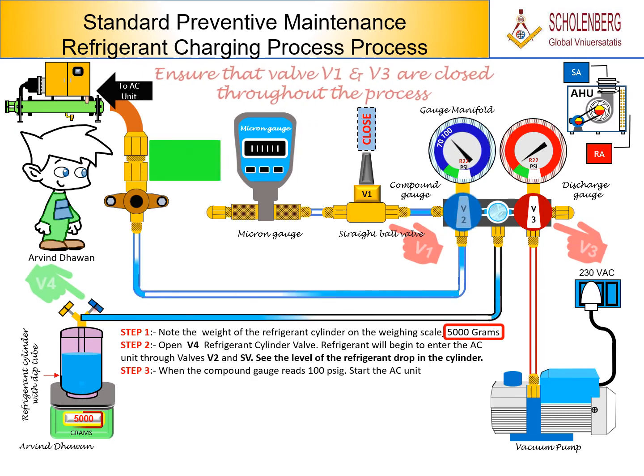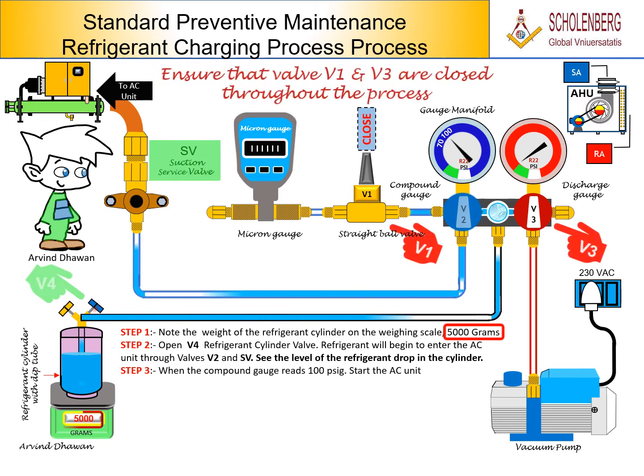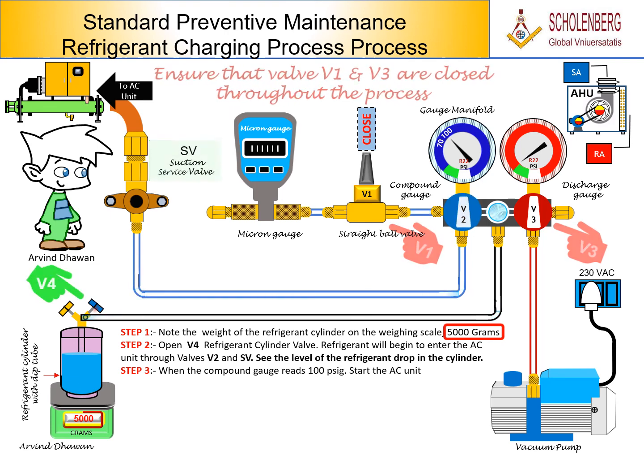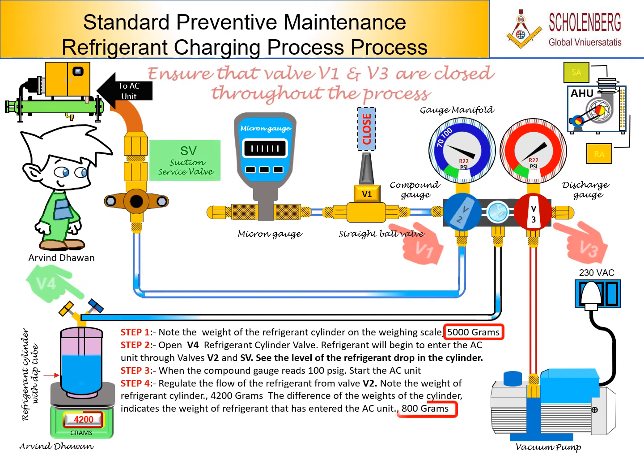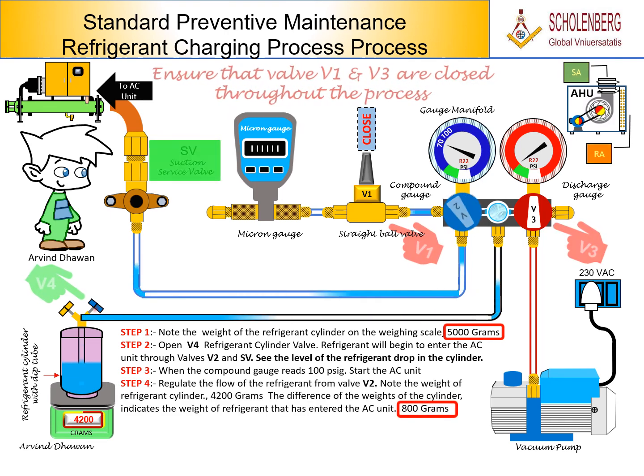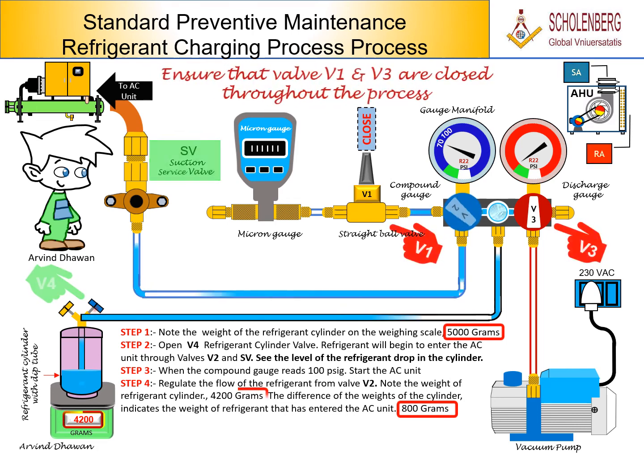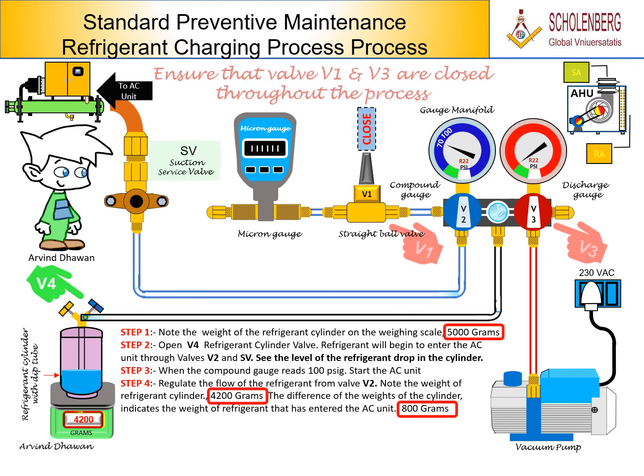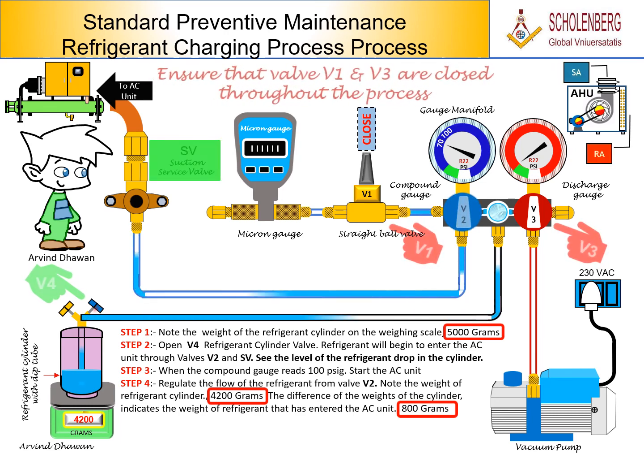Step 3. When the compound gauge reads 100 psig, start the AC unit. Step 4. Regulate the flow of the refrigerant from valve V2. Note the weight of the refrigerant cylinder, 4,200 grams. The difference of the weights of the cylinder indicates the weight of refrigerant that has entered the AC unit, 800 grams.